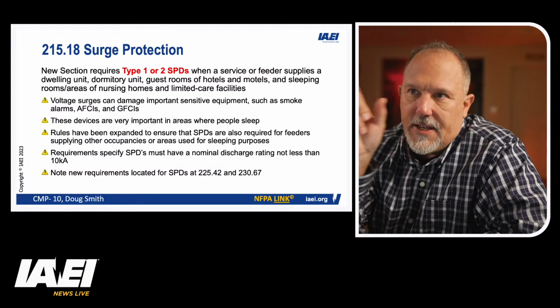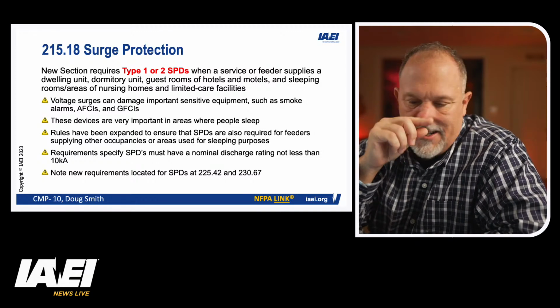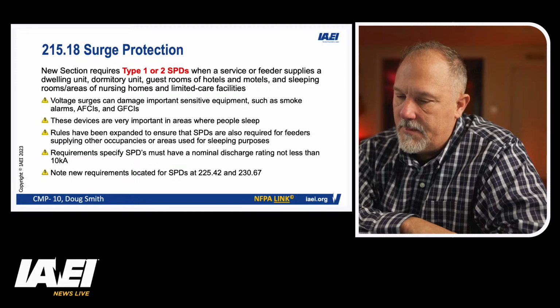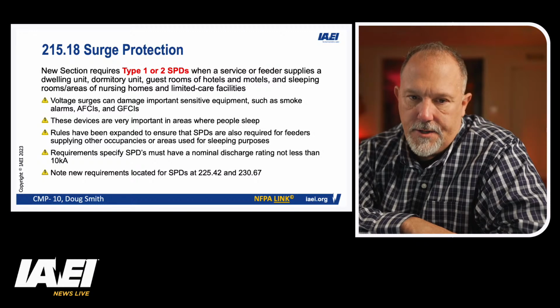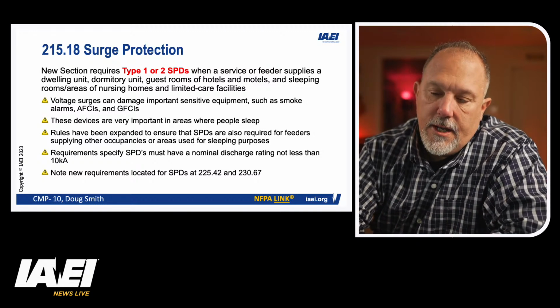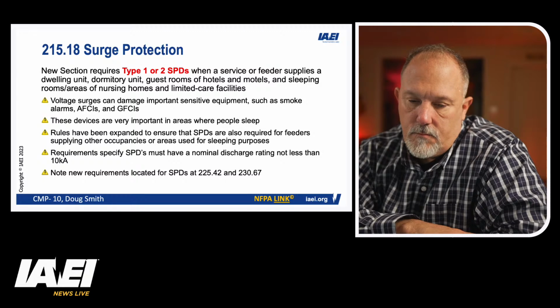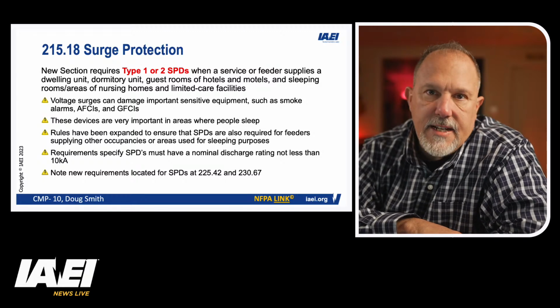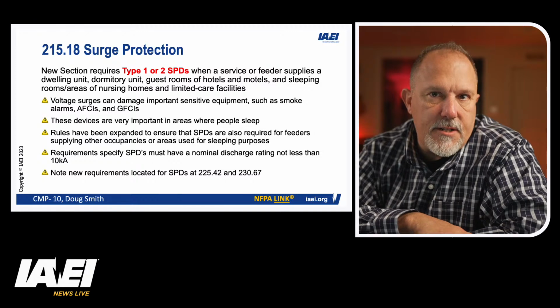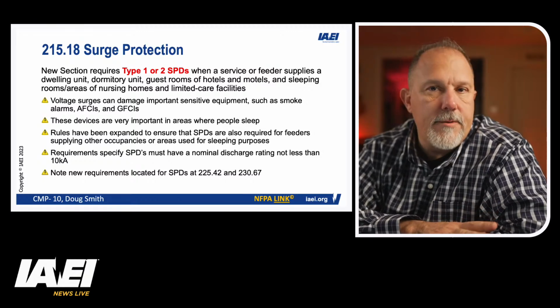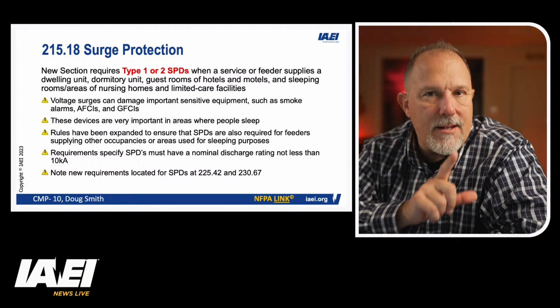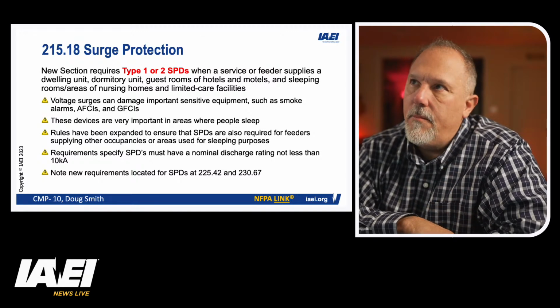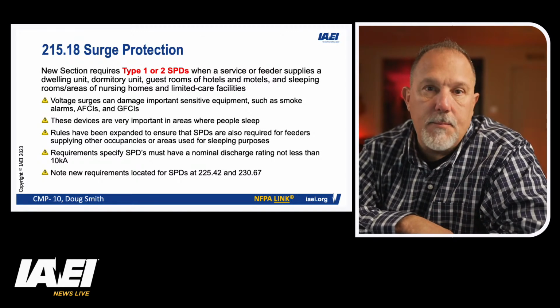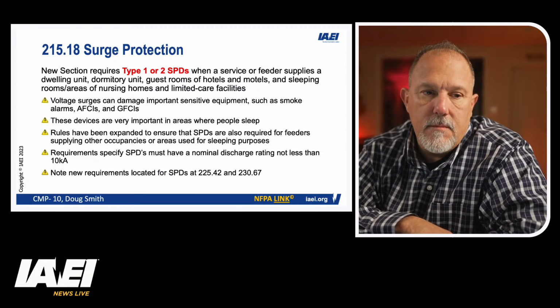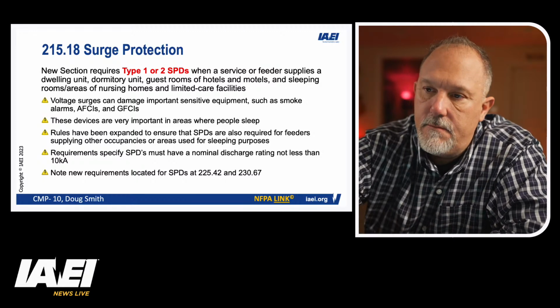The justification that was used, and I think a lot of people make the mistake here, is they say the reason you have surge requirements is because AFCIs and GFCIs and smoke detectors need to be protected. That's a good reason, but it's not the whole story. Remember, the code is not just about protecting personnel. The code is also about protecting equipment.